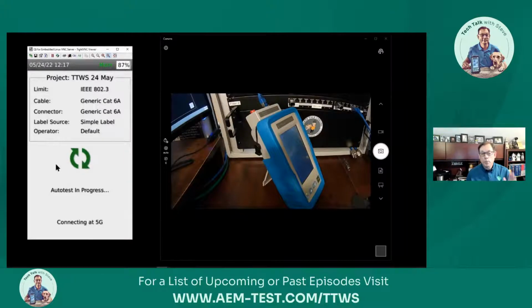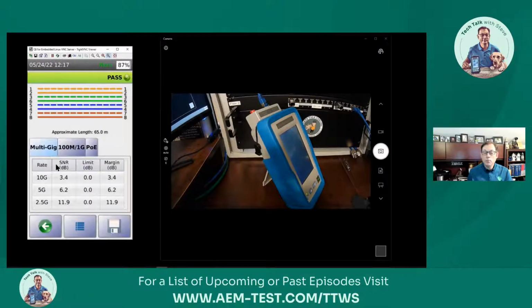While we're doing that, we're putting traffic on the wire, measuring the signal to noise ratio, and demanding PoE load all at the same time. So if PoE is present, we do a PoE load test as part of this auto test. We're measuring signal to noise ratio - comparing the level of the signal, the traffic on the line, with the noise. And you want a high number; the higher the number, the better when it comes to SNR.